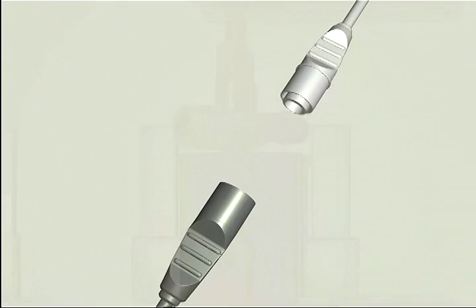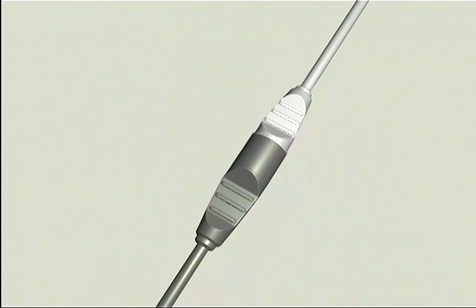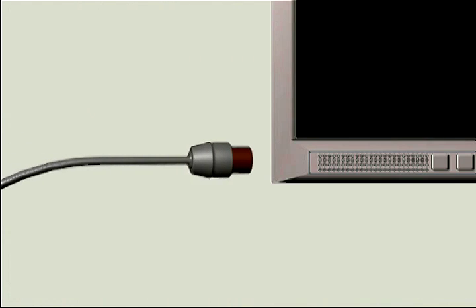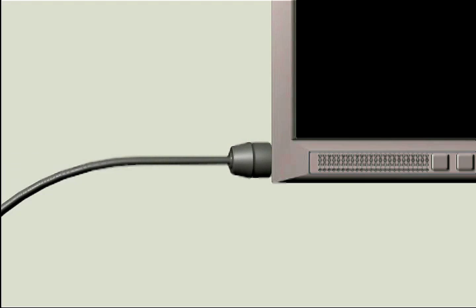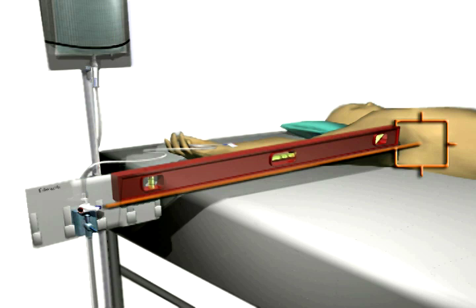Step 1. Connect the TruWave transducer's white connecting cable to the Edwards TruWave reusable pressure cable appropriate for the bedside monitor being used. Then connect the opposite end of the reusable cable to the appropriate pressure channel on the bedside monitor. Step 2. For intravascular pressure monitoring, level the transducer to the patient's phlebostatic axis, which can be found at the midpoint between the anterior and posterior chest wall at the 4th intercostal space.